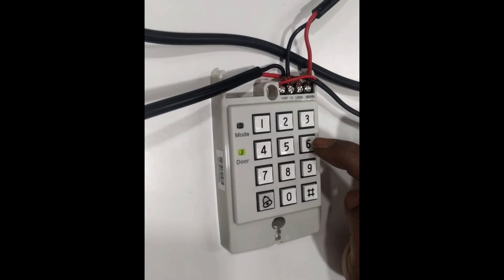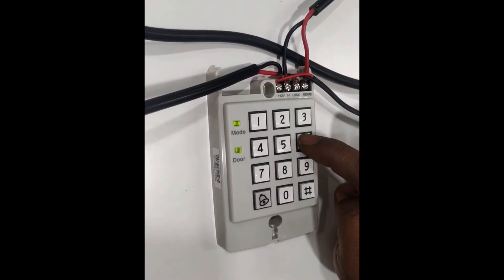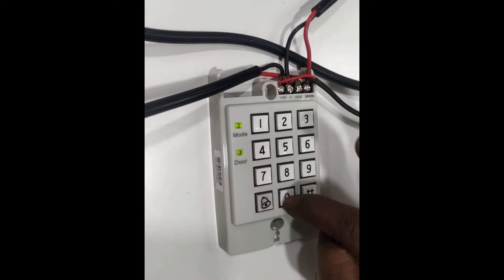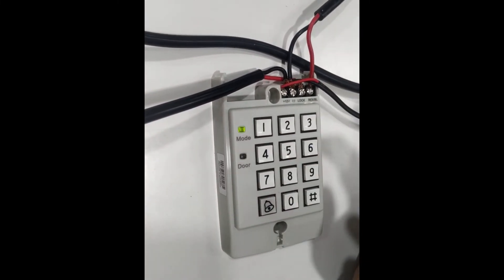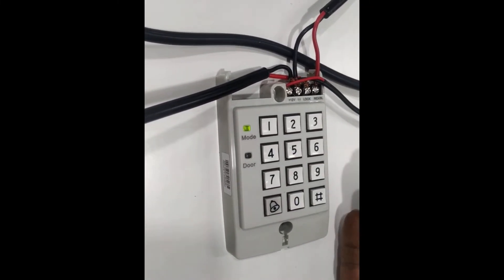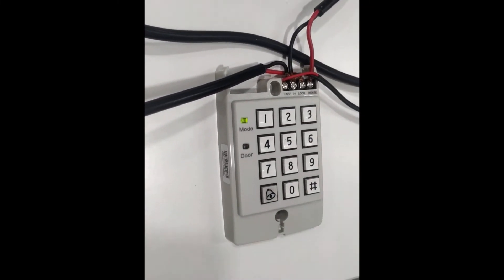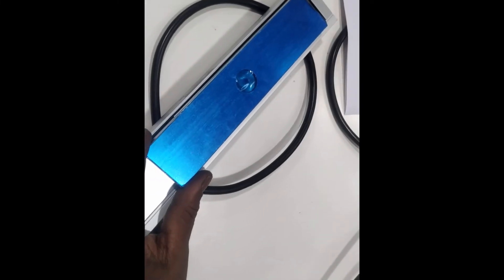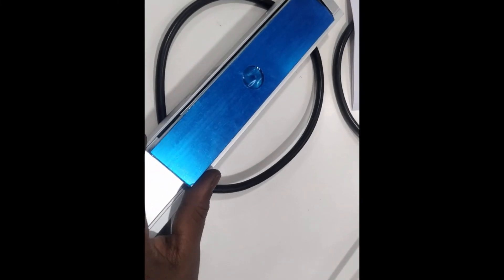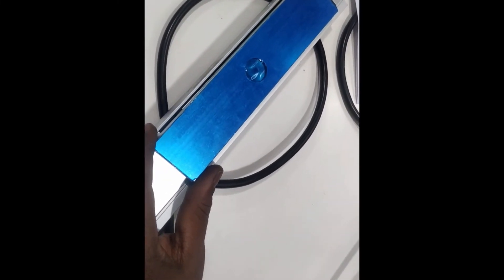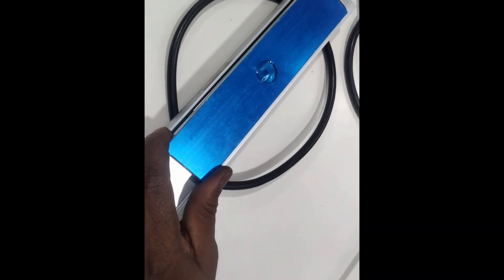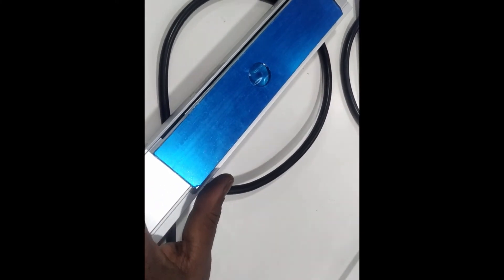Then lock style has changed. Now if we can see that EM lock gets energized, that means the lock style changed from NO to NC. So this is the basic function whenever we are connecting EM lock along with ACD32.